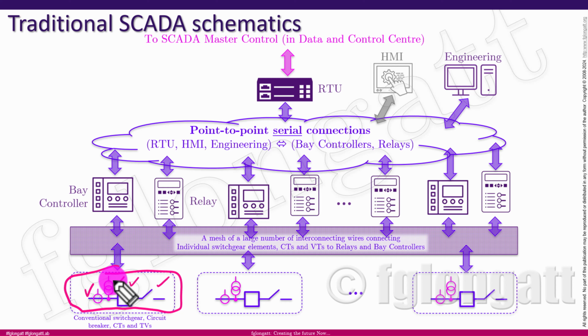All those devices are primary devices connected to the high voltage system. We have secondary circuits coming for measurements and automation, and a secondary circuit for tripping the circuit breaker. At the early stages of this technology, copper wires were used, and some substations still use copper wires to transmit commands or signals from those current and voltage transformers.